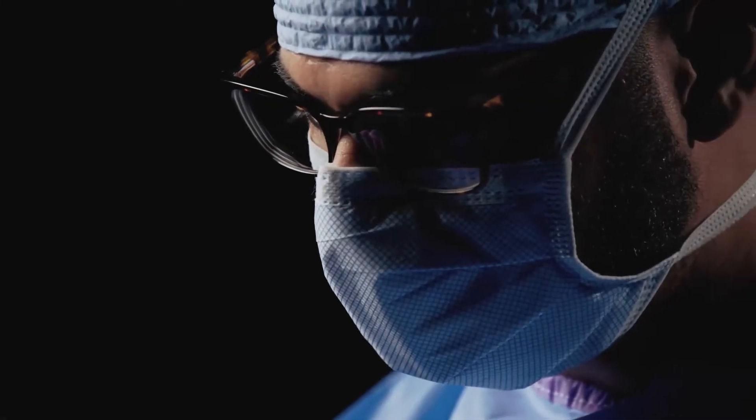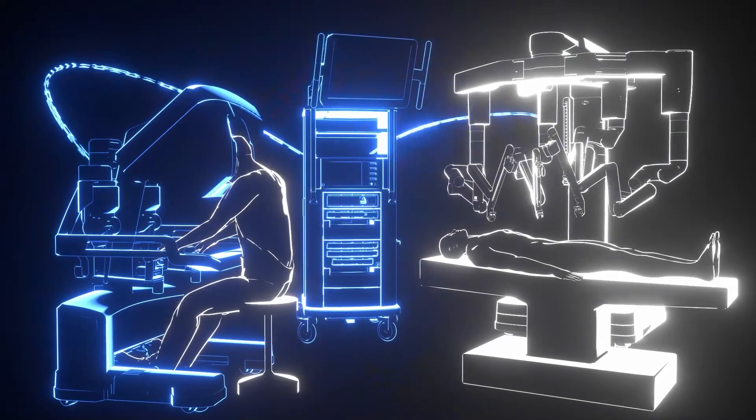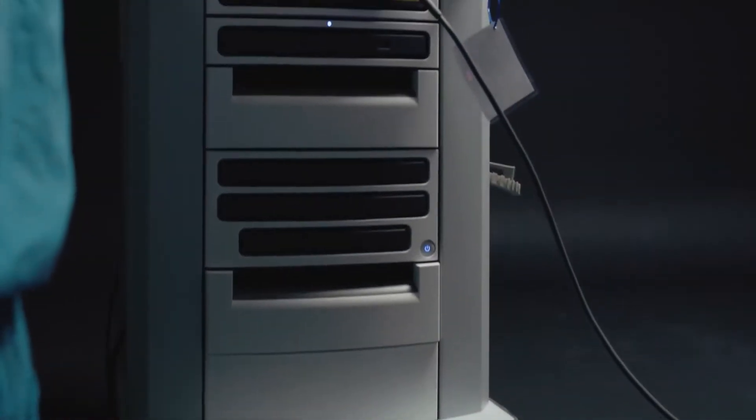The time between what's going on in the surgeon's hands and what's going on inside the patient is called latency, and that latency needs to be measured in milliseconds for things to be safe. So when I'm operating, I may see some tissue bleeding, and if I don't react by stopping it — grasping and cauterizing it — that could be a serious problem. Removing latency from the system at the millisecond level is a constant battle. So much work goes into making the software code as efficient as possible and ensuring the signal travels via fiber optic cables as fast as possible from one component to another. The more latency, the less safe this is.